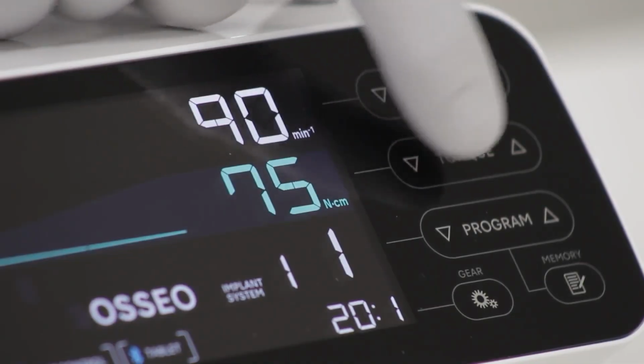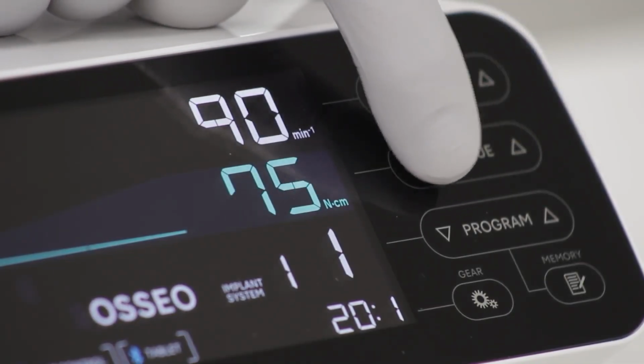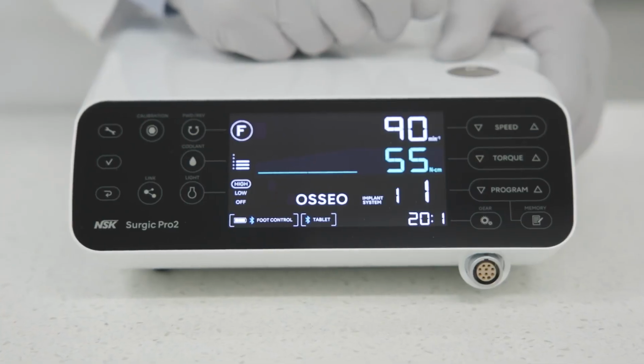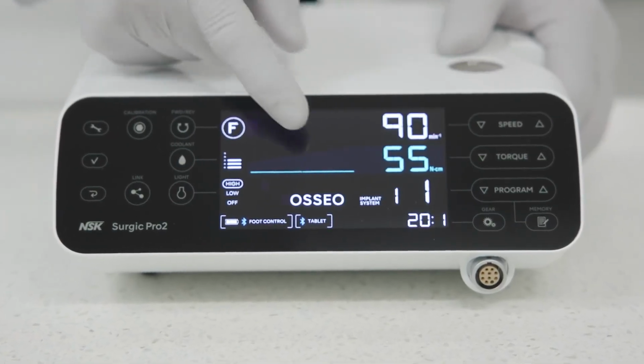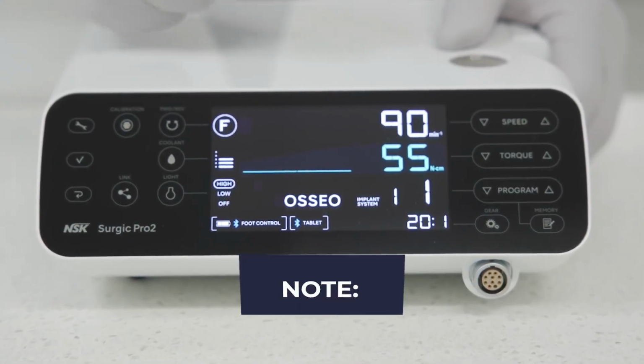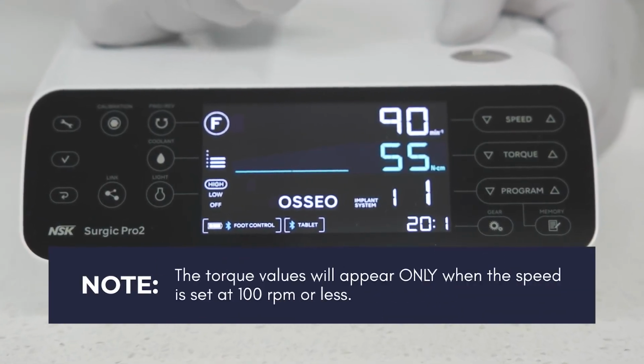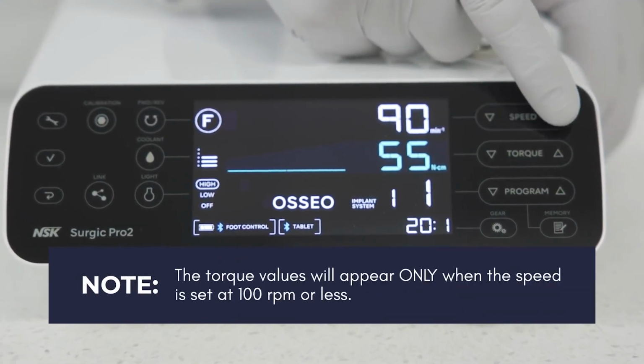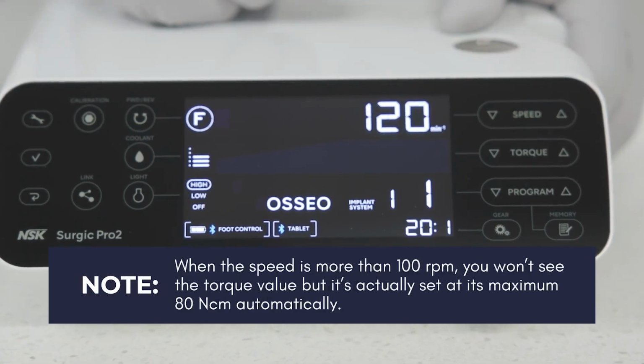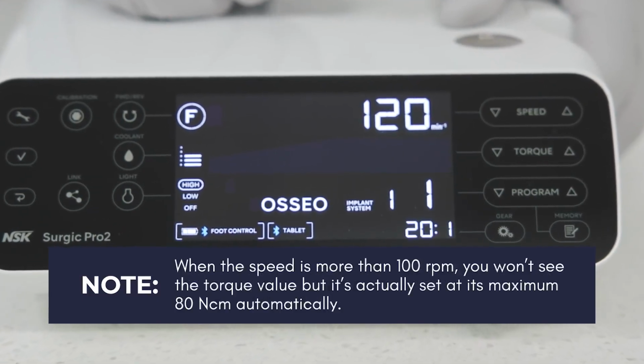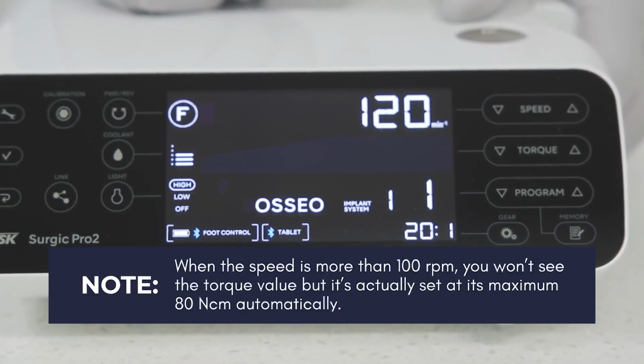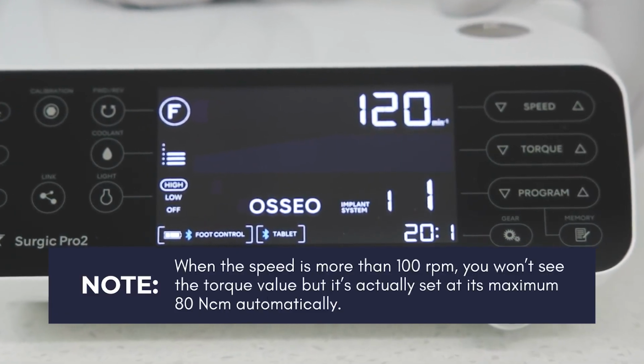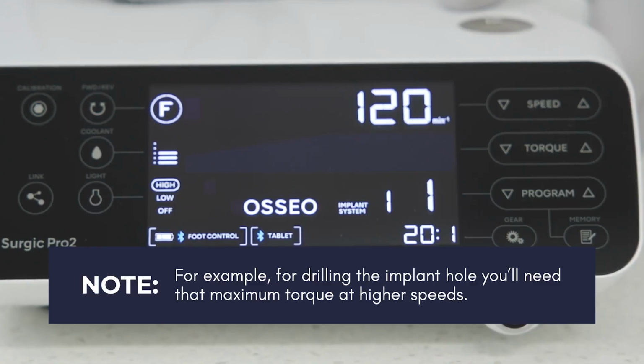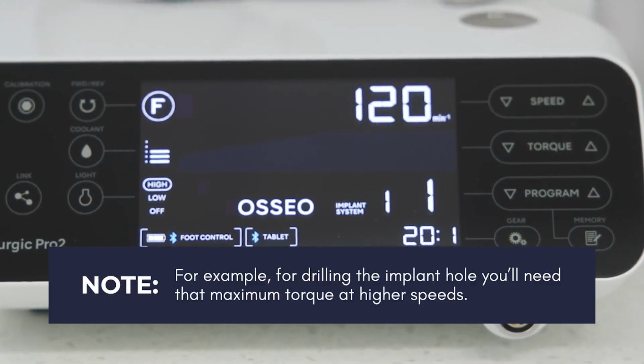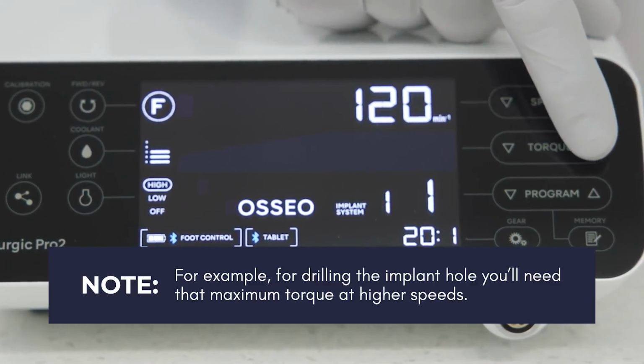Torque buttons are used to change or set the torque values between 5 and 80 Newton centimeters for implant handpieces. The current operating torque is displayed here like a graph during operation. Note: the torque values will appear only when the speed is set at 100 RPM or less. When the speed is more than 100 RPM, you won't see the torque value, but it's actually set at its maximum 80 Newton centimeters automatically. For example, for drilling the implant hole, you'll need that maximum torque at higher speeds.